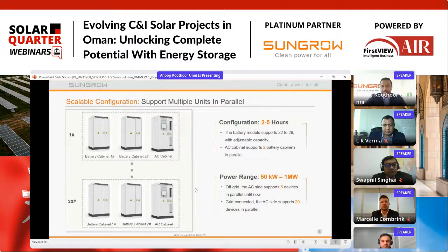When we're talking about products in parallel connections, as we know, market requirements sometimes vary from off-grid to on-grid and different application scenarios. For off-grid applications, we can scale up to a maximum of 6 units in parallel, and for on-grid applications, we can do paralleling of 20 units. The batteries can support either one PCS with two batteries, or one PCS with one battery, or a lot of combinations, depending on load requirements. The designing engineers can do a lot of combinations depending on the system design as well as analyzing the load profile of the site's actual conditions.